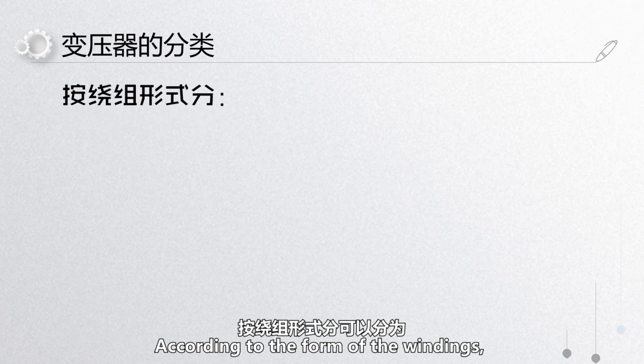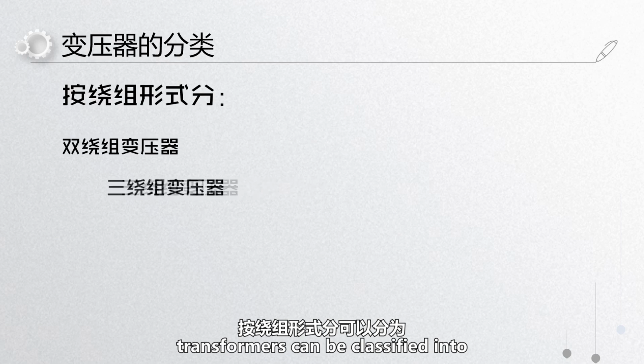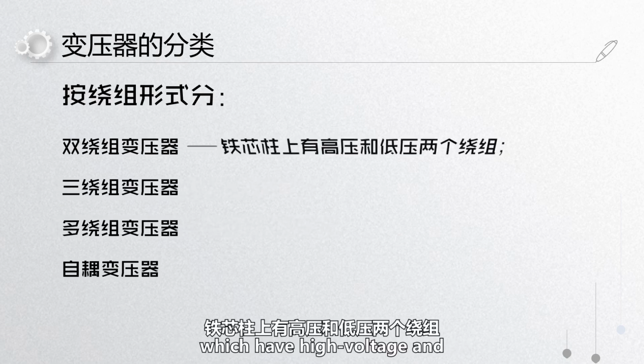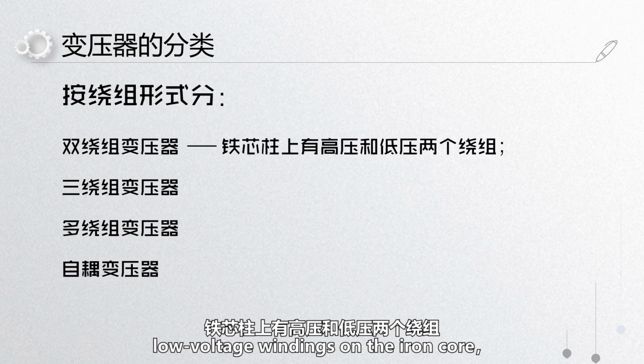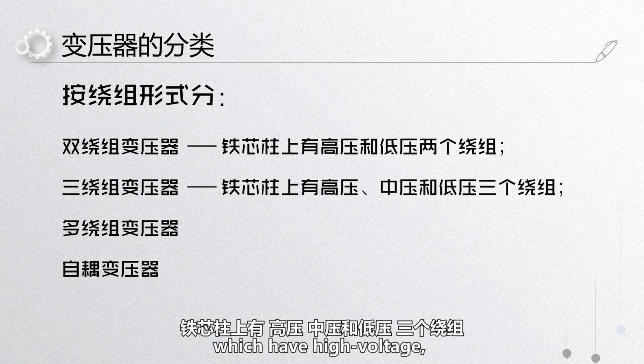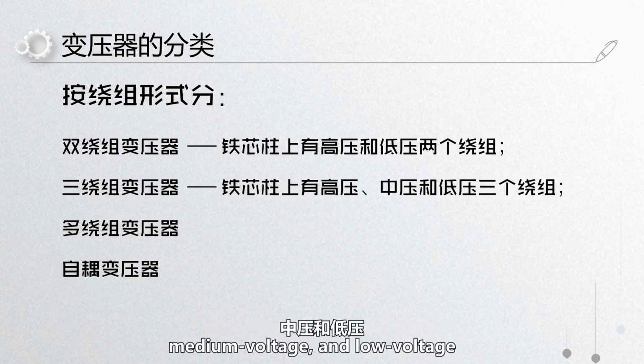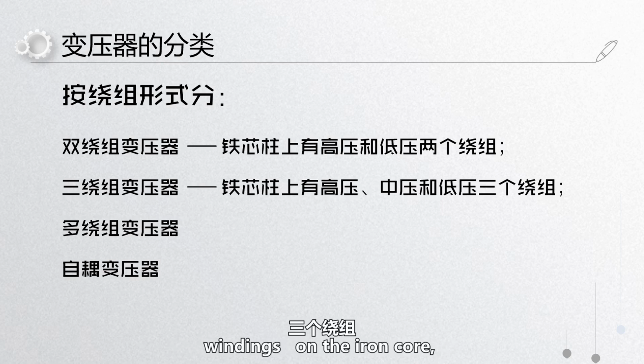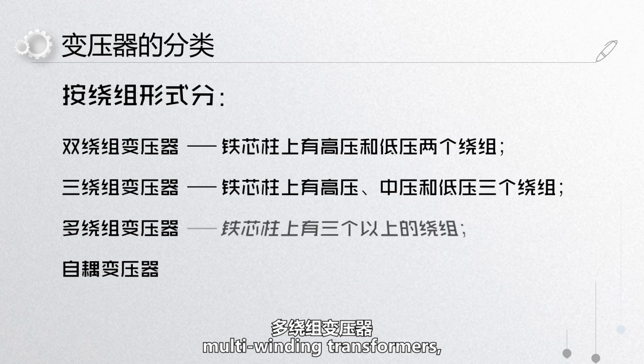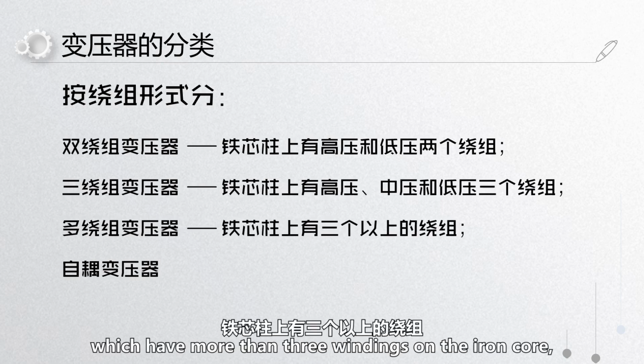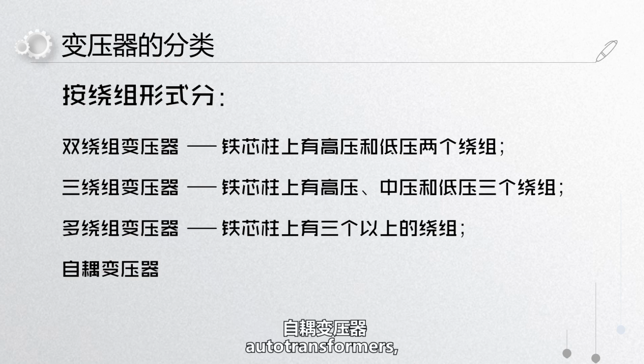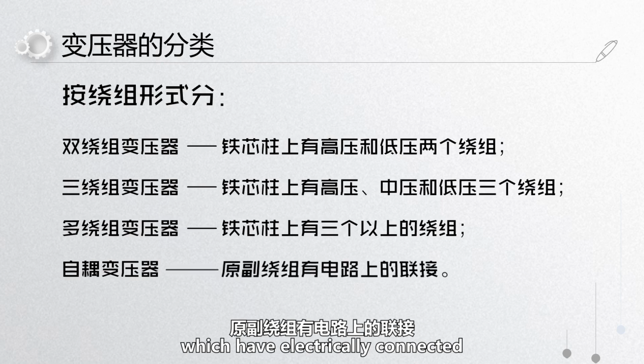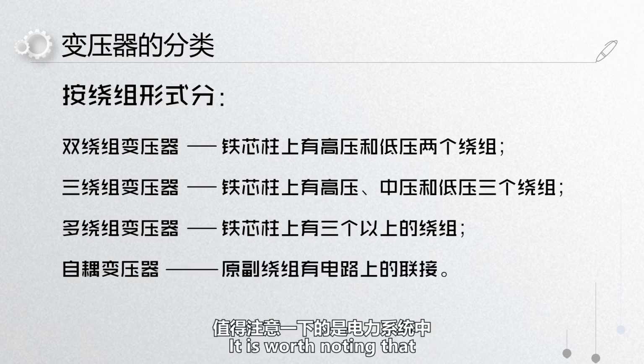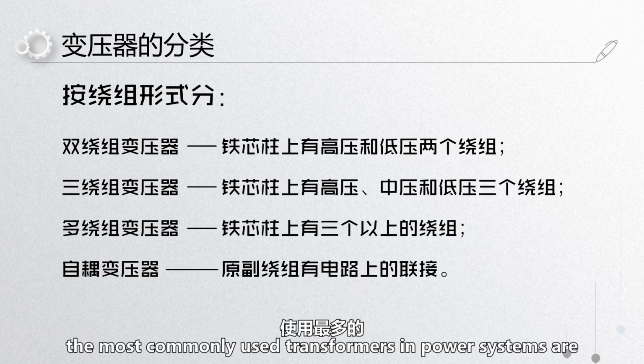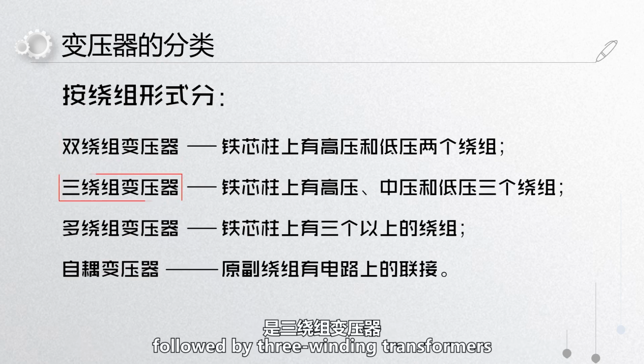According to the form of the windings, transformers can be classified into double-winding transformers, which have high voltage and low voltage windings on the iron core. Three-winding transformers, which have high voltage, medium voltage, and low voltage windings on the iron core. Multi-winding transformers, which have more than three windings on the iron core. Auto transformers, which have electrically connected primary and secondary windings.